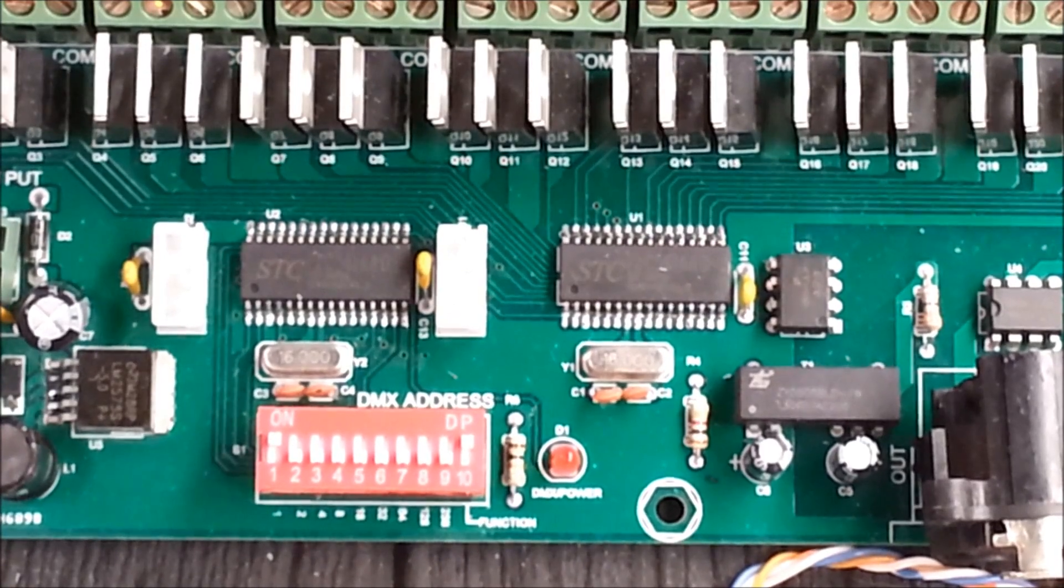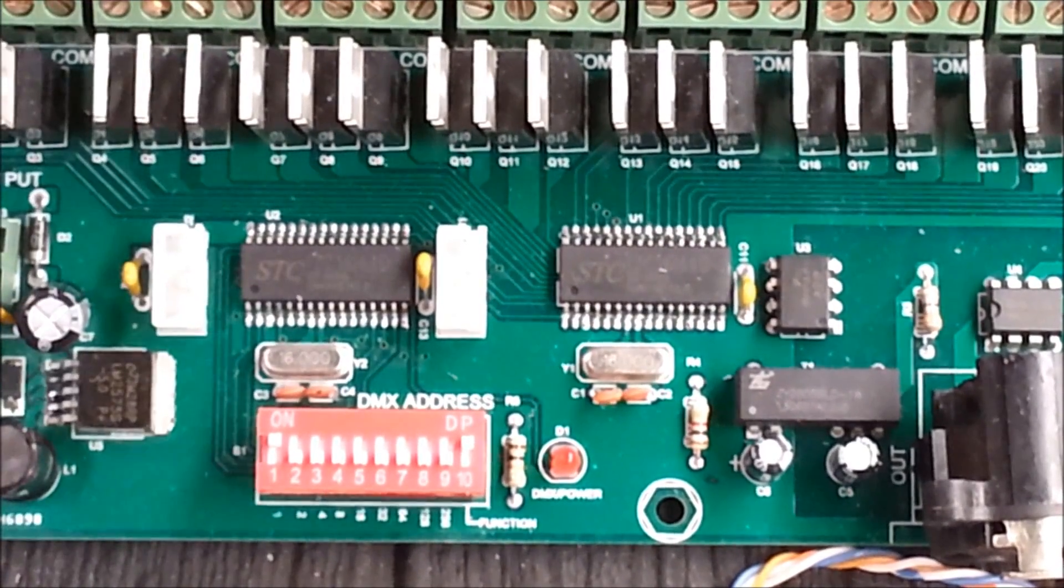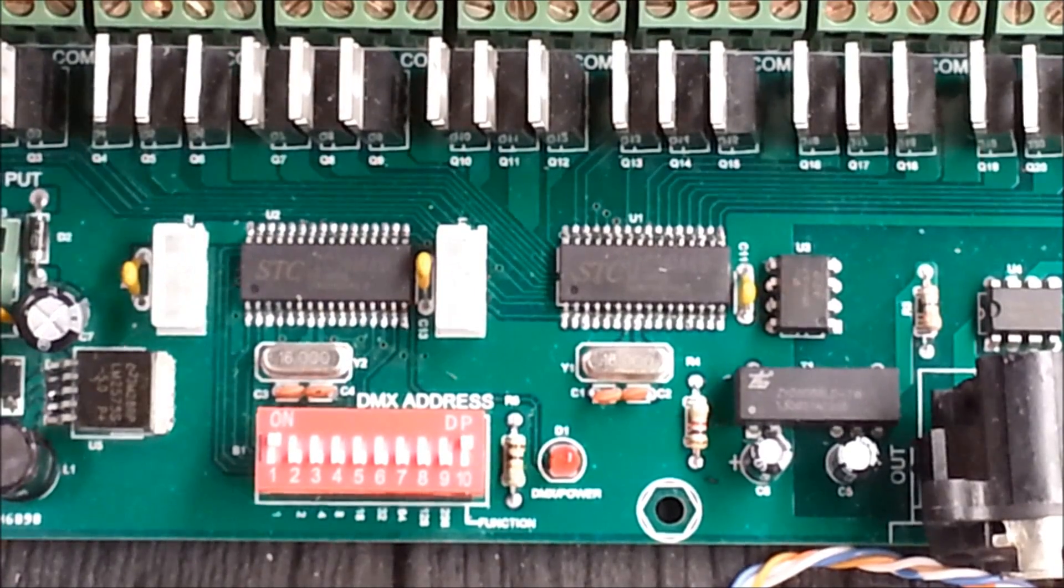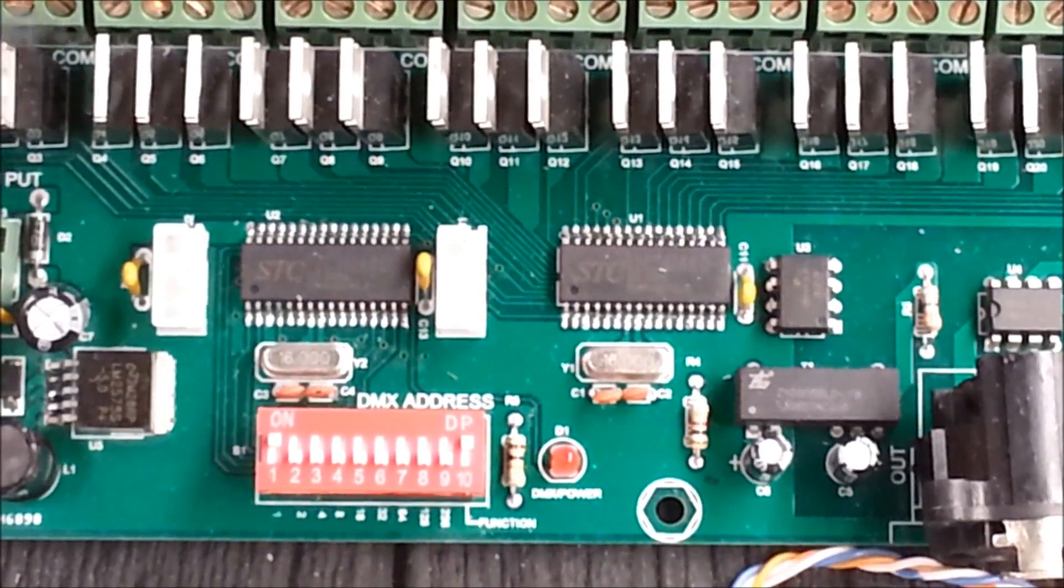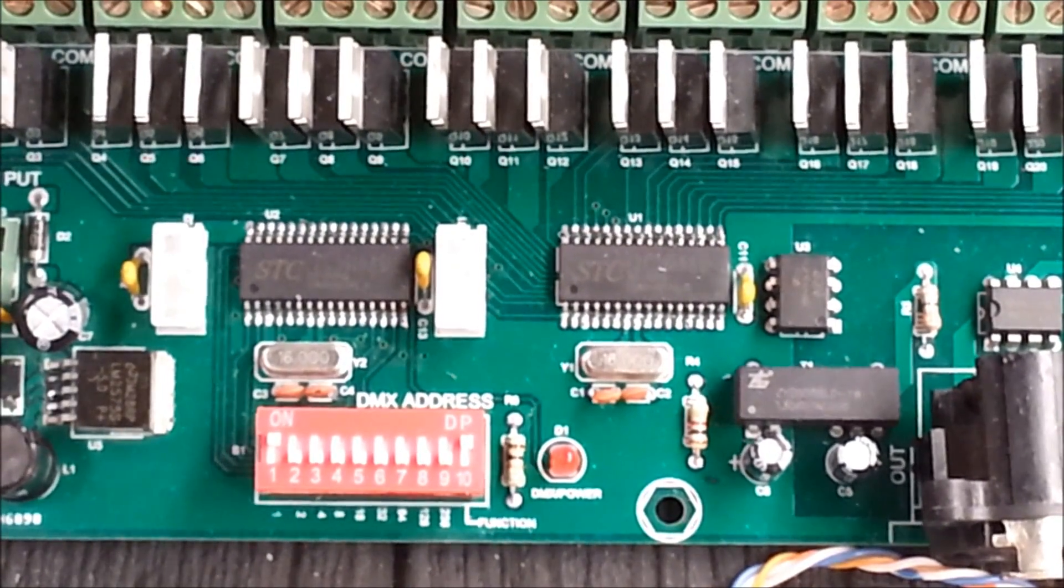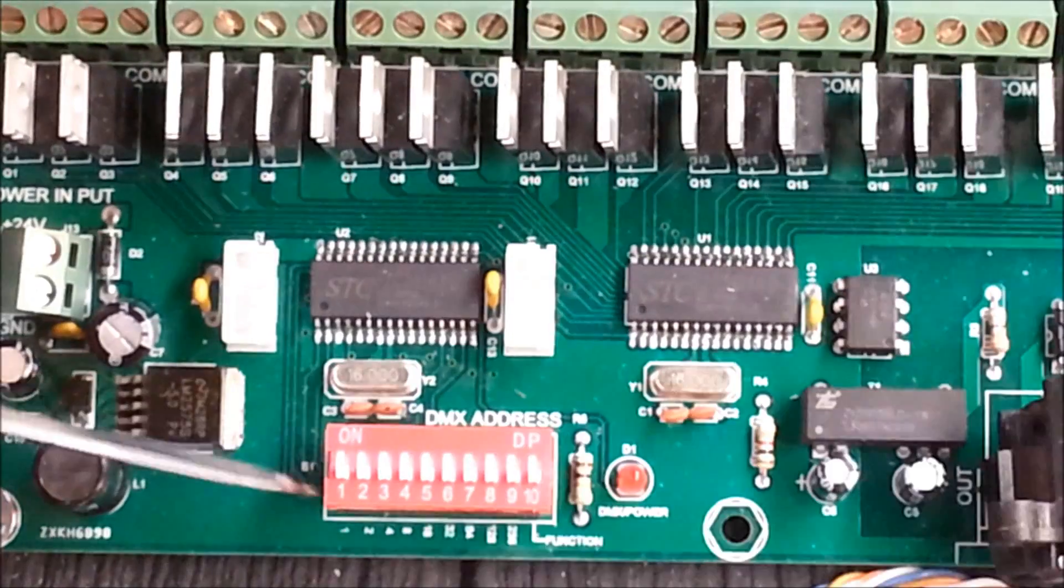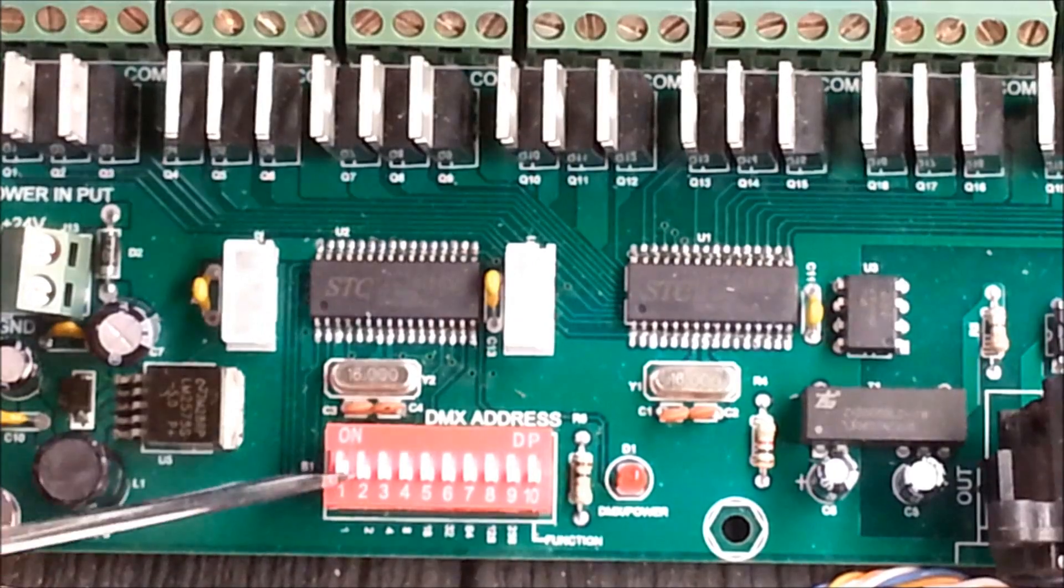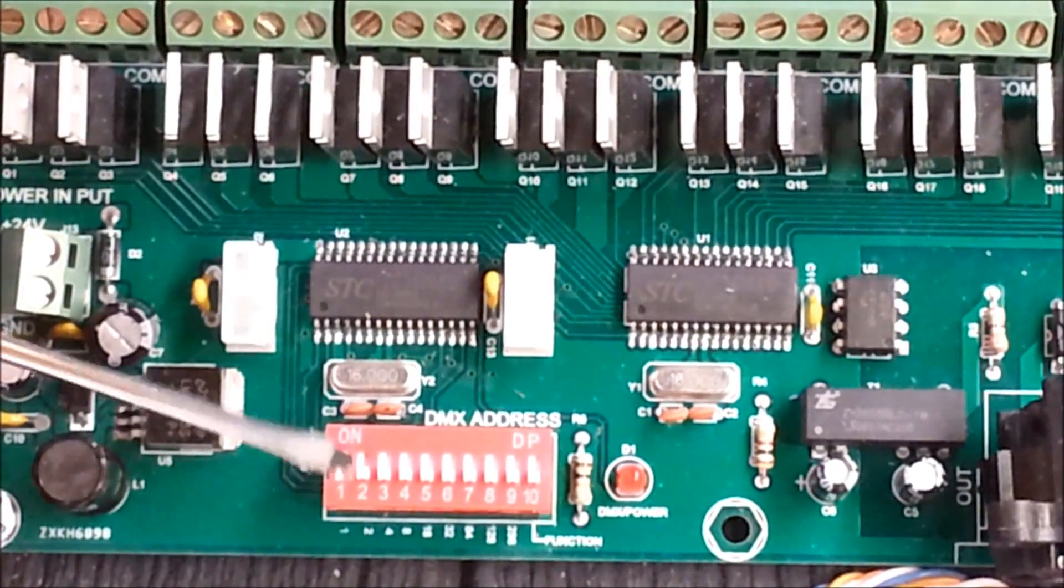Since for our test, we're going to run this controller with the other controller, I need to set these dip switches so that this controller believes that it is controller number one, where the first output right here, up in the top left, the first output there, thinks that the red channel is channel number one. To make this channel number one, I'm going to set dip switch setting to number one on.